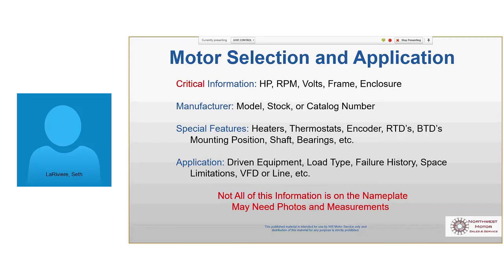What's the horsepower, RPM, volts, frame, enclosure? If you've got a manufacturer part number, a Baldor EM 3711G, that helps because then we can find that exact one or cross that to something that we have on the shelf. Also, if you could tell us if it has any special features, heaters, thermostats, RTDs, an encoder, anything like that, special bearings, roller bearings, that's something that we want to know to make sure we select the right motor.